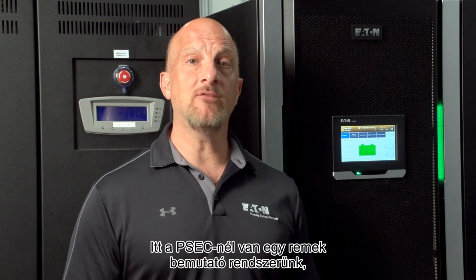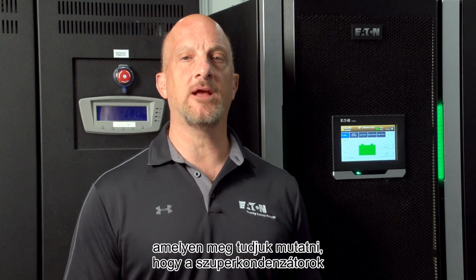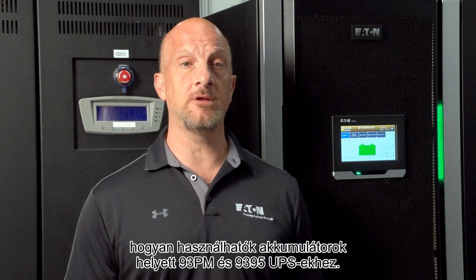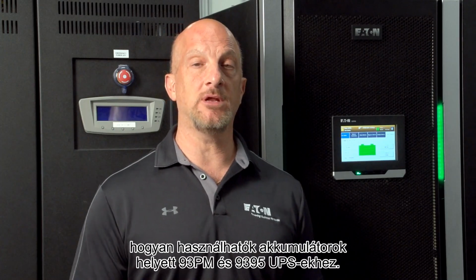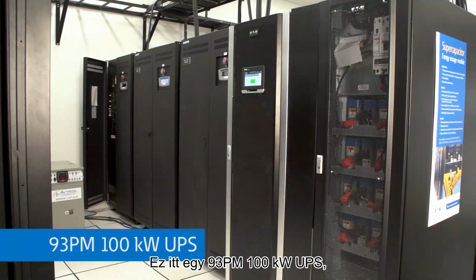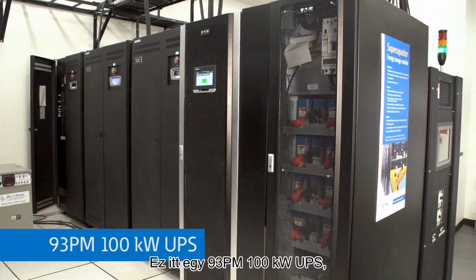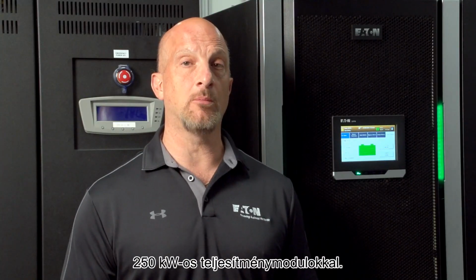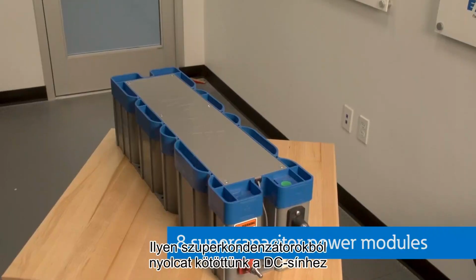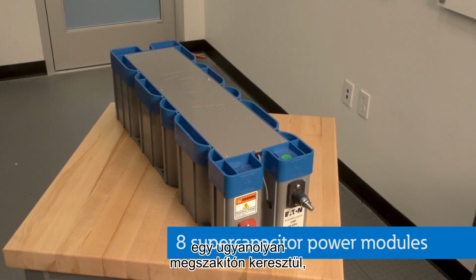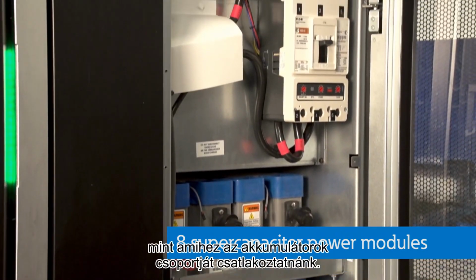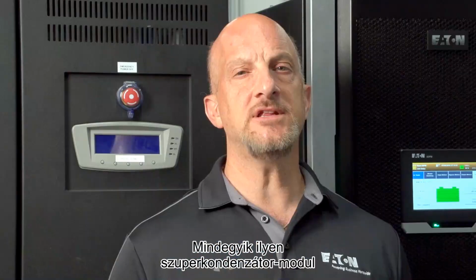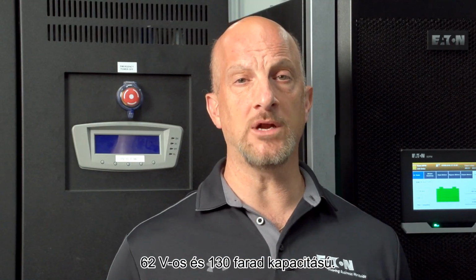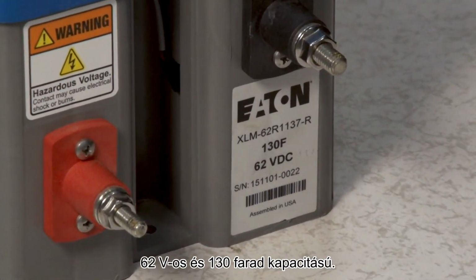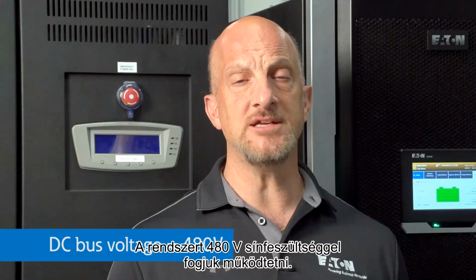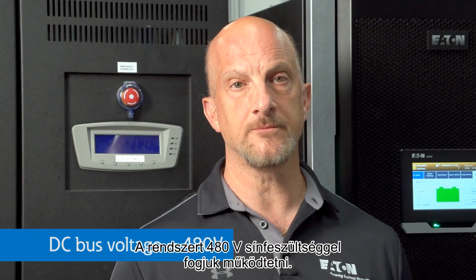Here at the PSEC, we have a great demo set up to show how supercapacitors can be used as a battery replacement for 93 PM and 9395 UPSs. This is a 93 PM 100 kilowatt unit with two 50 kilowatt power modules. We've attached 8 of these supercapacitors to the DC bus via the same breaker you would attach a string of batteries to. Each of these supercap modules is rated 130 farads and 62 volts. We'll operate at a DC bus voltage of 480 volts.